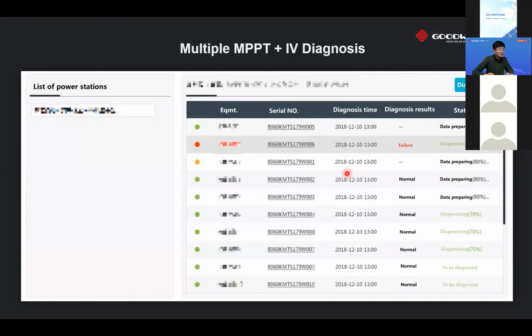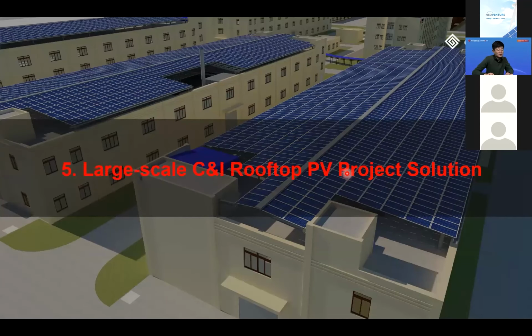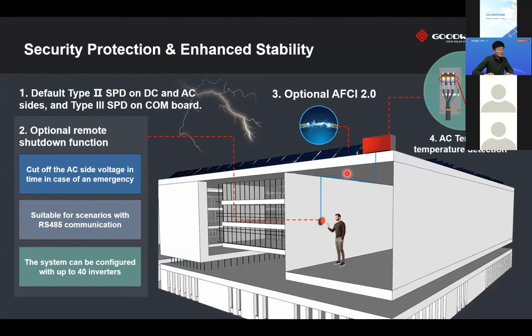Just a sampling here. And this scenario is about large C&I rooftop PV projects. We know that for C&I PV projects, a very important and critical thing is safety. We design our products with type 2 SPD on both DC and AC sides, even type 3 SPD on the communication board. So it is very safe for everybody, within the instructions and constructions. And we designed the AFCI, already upgraded to the second generation, so it is very safe to control the PV array system operation. And we also integrate AC terminal temperature detection in the PV inverters.